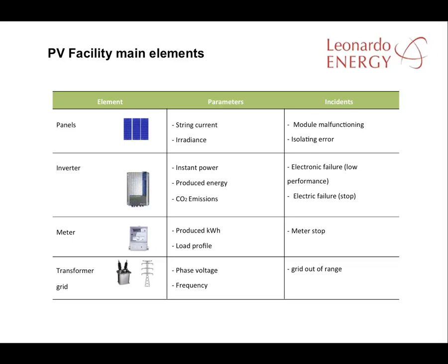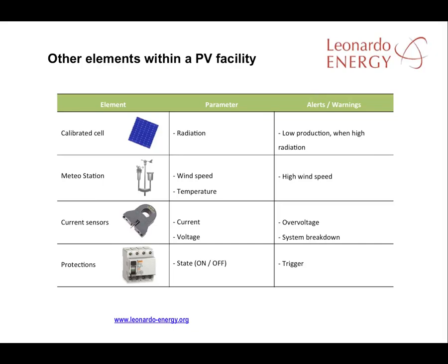The panels and transformers should also be monitored. On the panels you can monitor both the current and the irradiance. The current is quite easy to monitor with devices that are readily available in the market. You can detect solar panels that are producing lower electricity than they should using a calibrated cell to measure irradiance. The meteorological station will give you measures of wind speed and temperature. Temperature has a direct effect on the solar panels' production capacity.